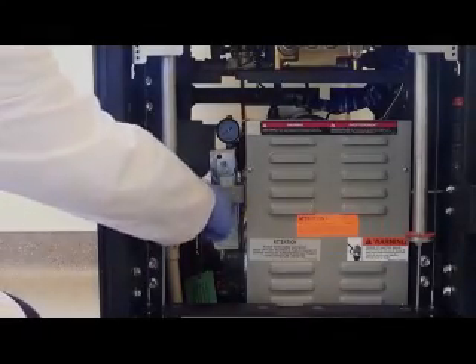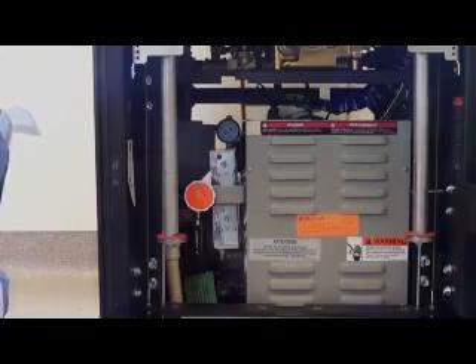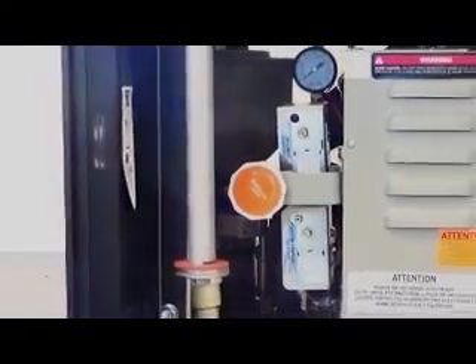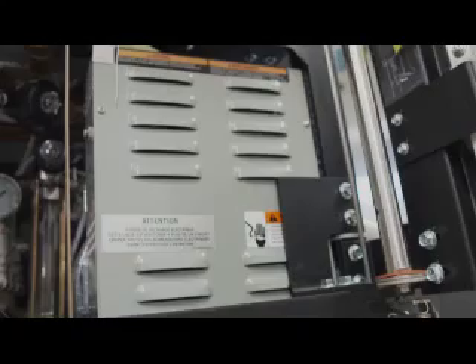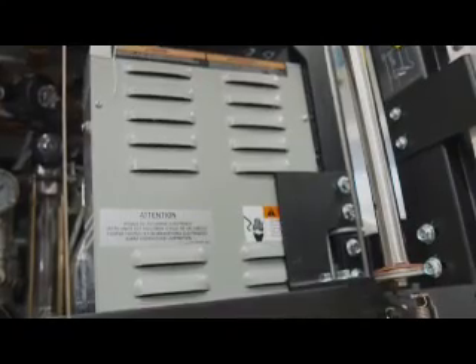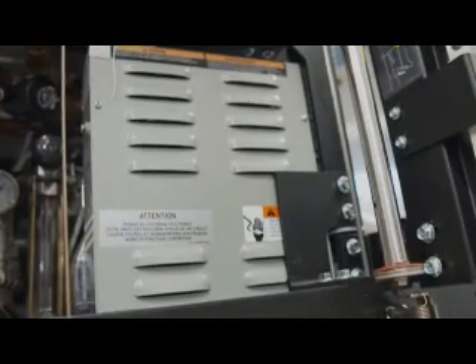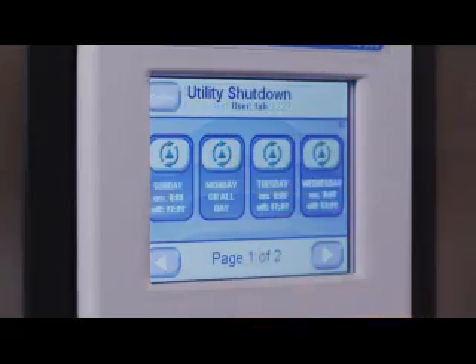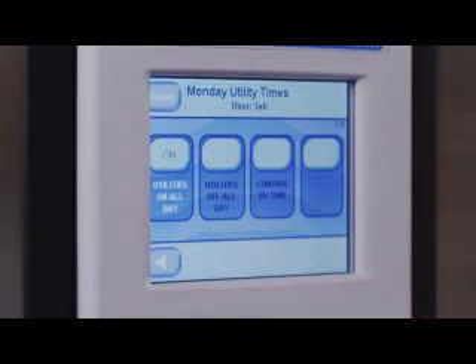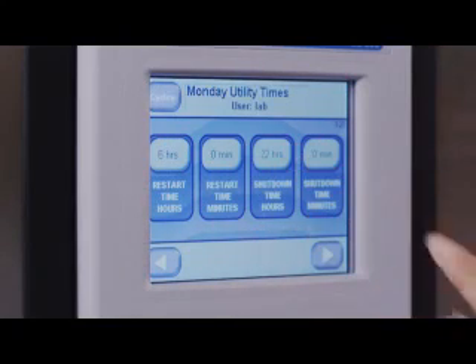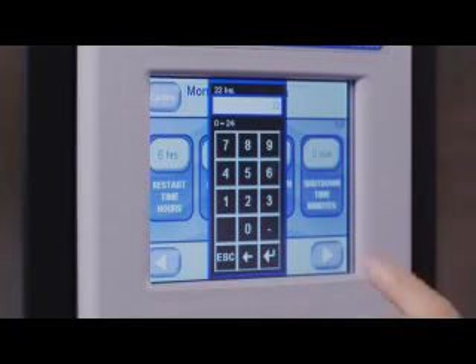For those sterilizers that are equipped with their own integral carbon steel steam generator, daily flushing is necessary to prolong the life of the steam generator's heating element. Some units are purchased with a mechanism that automatically flushes the generator. This will occur first thing in the morning when the sterilizer is started. Because this automatic flush can only be performed when the generator is cool, please ensure that you have scheduled a shutdown time for the sterilizer.